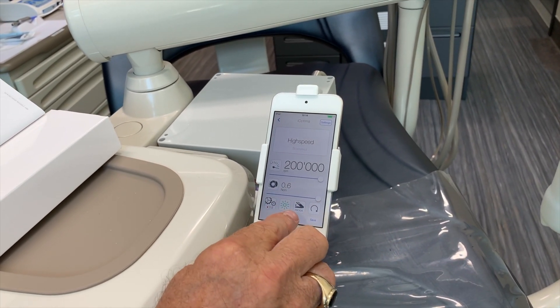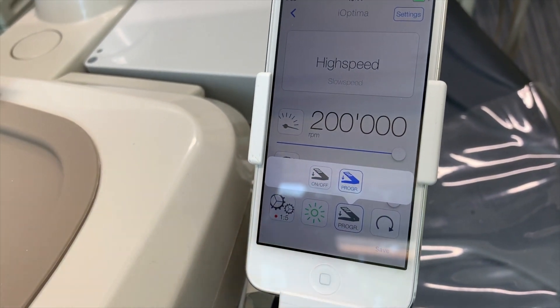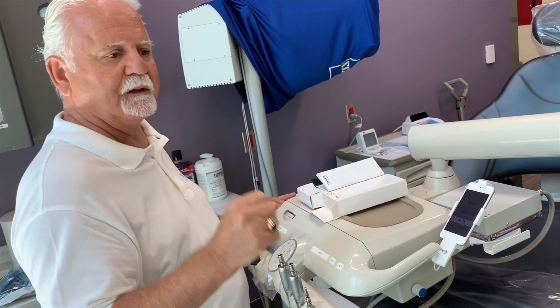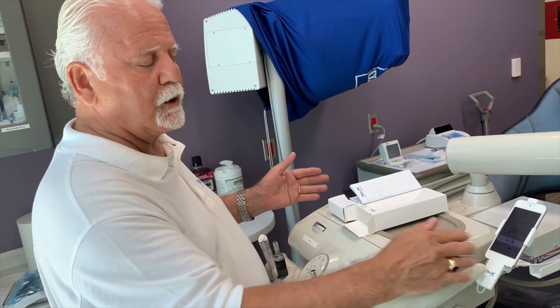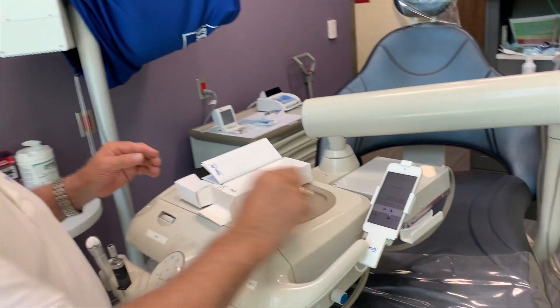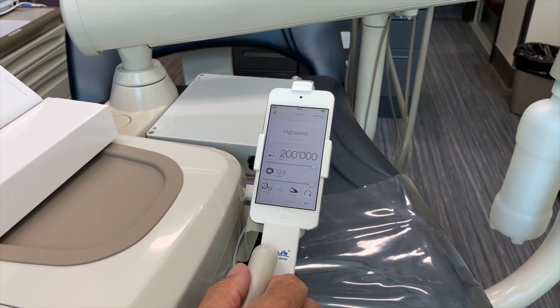Forward reverse. We can use the foot control in two ways: a simple on/off, or progressive, which is a real rheostat increasing the speed — the more you press the pedal, the faster it'll go, like a gas pedal. In endodontics, by default it's set to on/off because you don't want to vary the speed when doing endo. But if for whatever reason you'd like to control the speed during endo, just go to the setup and change from on/off to progressive foot control, as simple as that. Then you can save all of your presets.